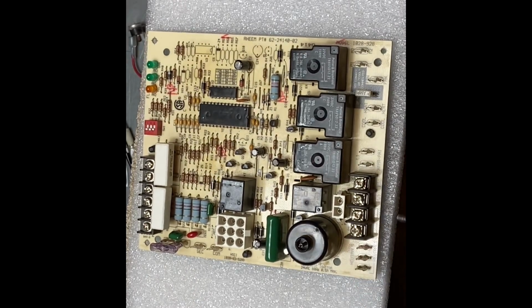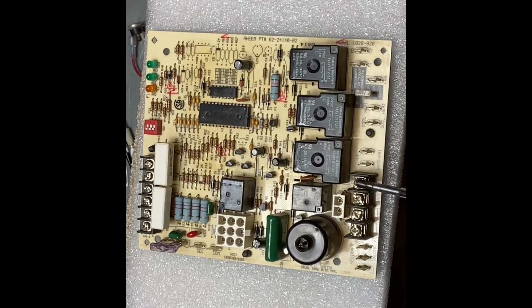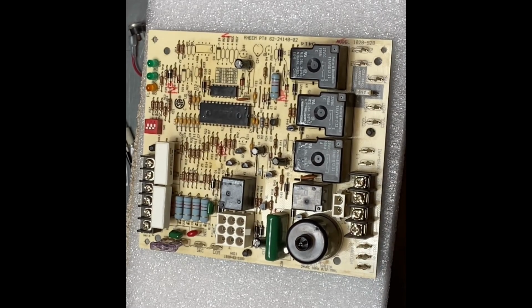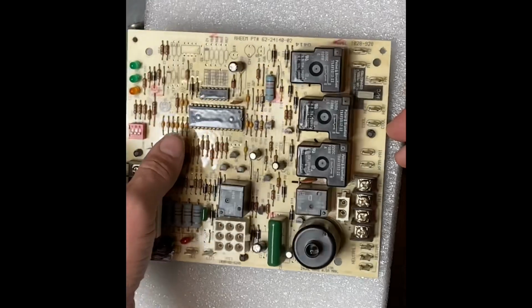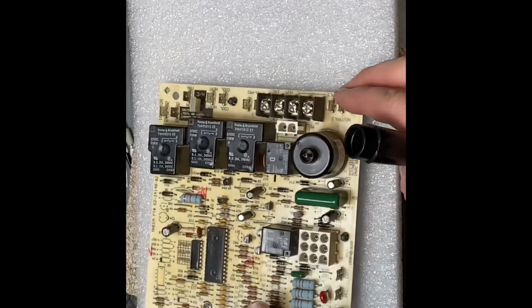So this would be for an accessory for a humidifier. And then some units had an electronic air cleaner. So we would energize that from here and also neutral and run the accessories for that unit. So we're going to continue on. I'm going to turn this board so you can see it a little bit better.